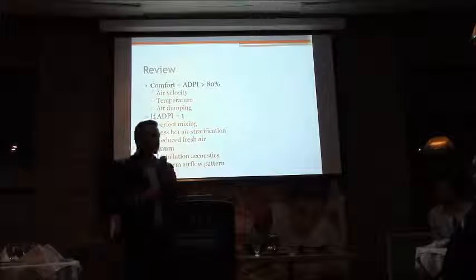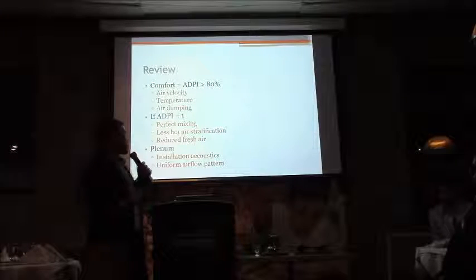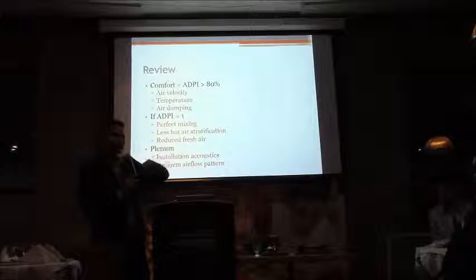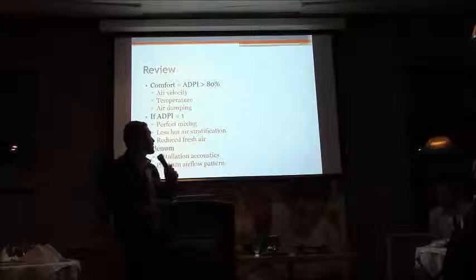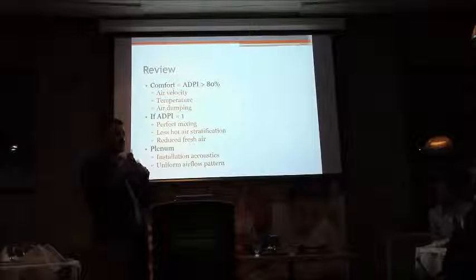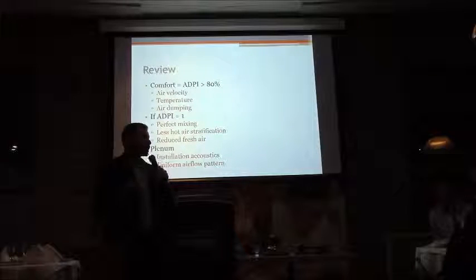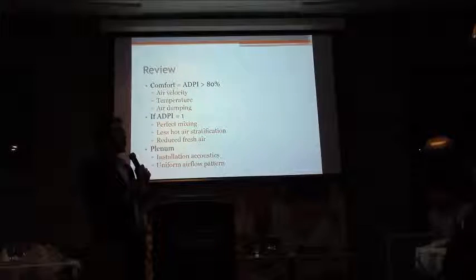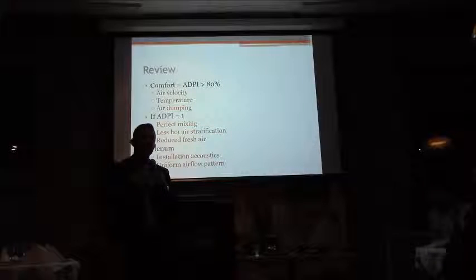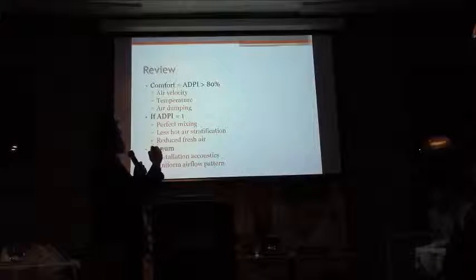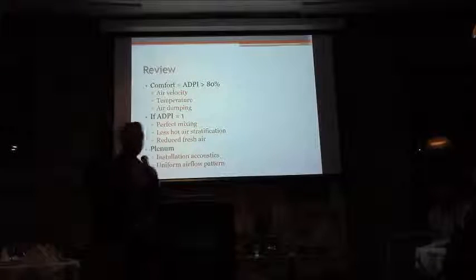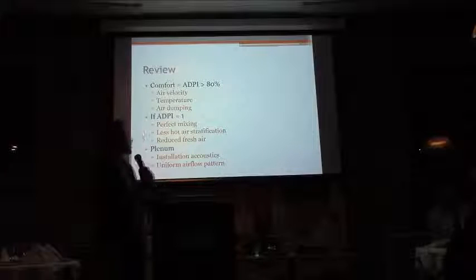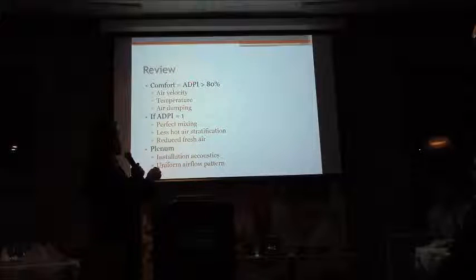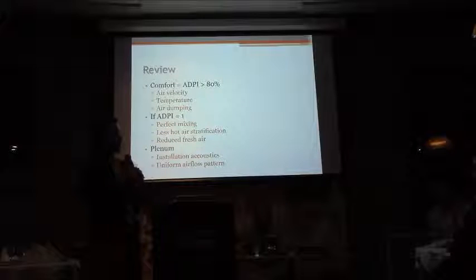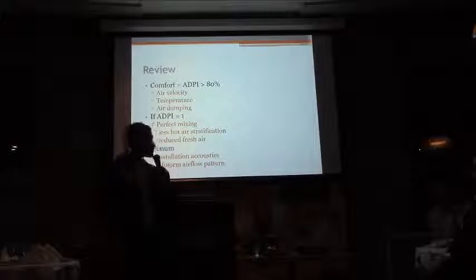So yeah, that's pretty much it for the presentation. I think it was much less than an hour. So just want to recap. Basically, what defines comfort? It's ASHRAE standard 55, and to rate the efficiency of your HVAC system, it's through ADPI, and you want to have ADPI always over 80%. That depends on your air velocity, your temperatures, and you want to avoid at all costs cold air dumping.